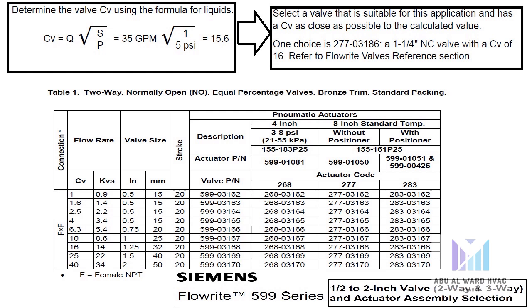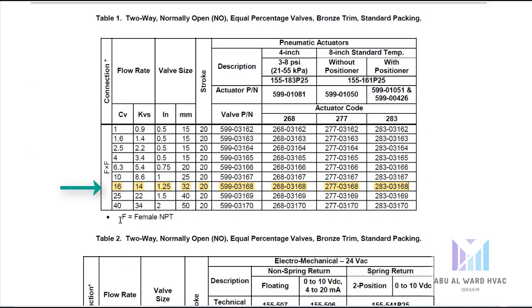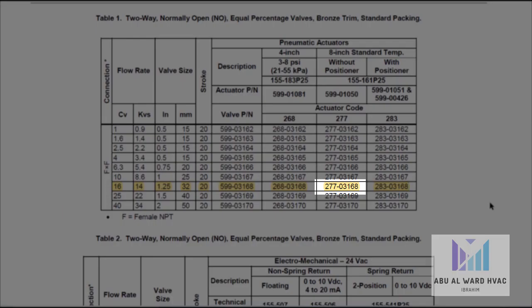From the valve specification, the valve is a two-way normally open equal percentage valve with bronze trim and standard packing. According to a Cv value of 16, we can find the valve for the 8-inch standard temperature actuator. The pneumatic actuator code is 277-03168. This is the full description of what we have selected according to the steps discussed.